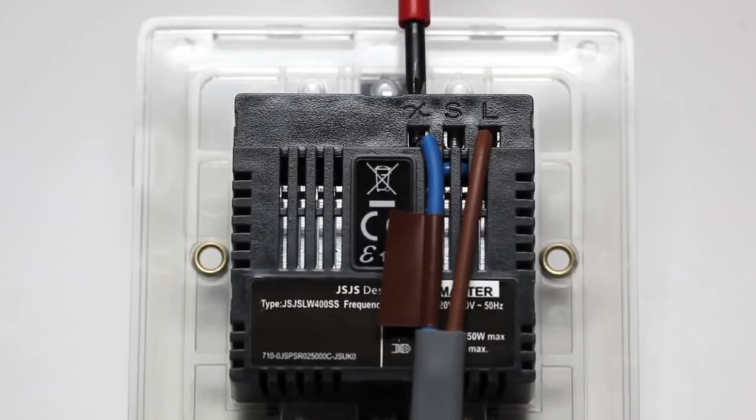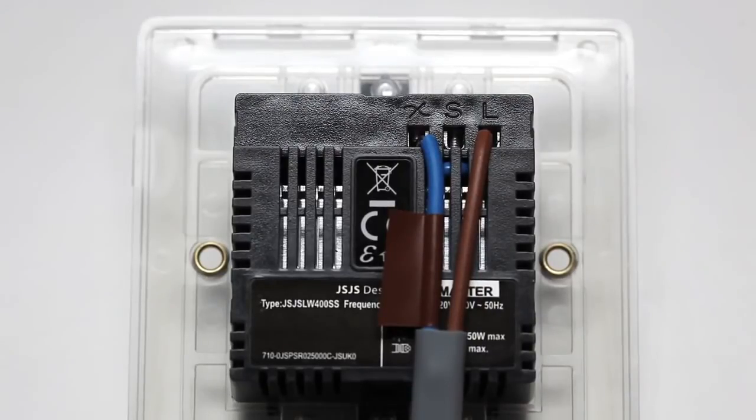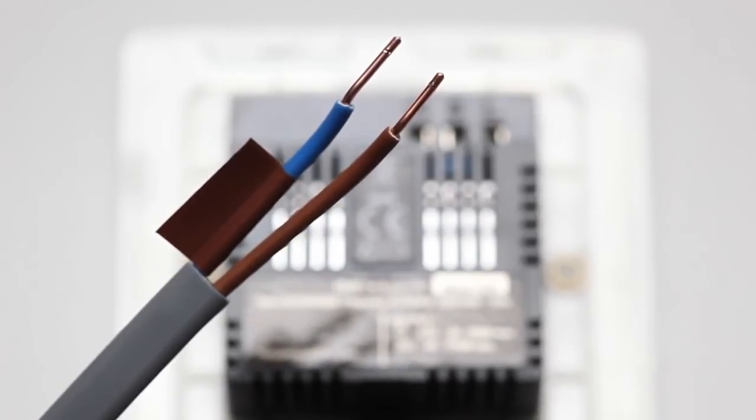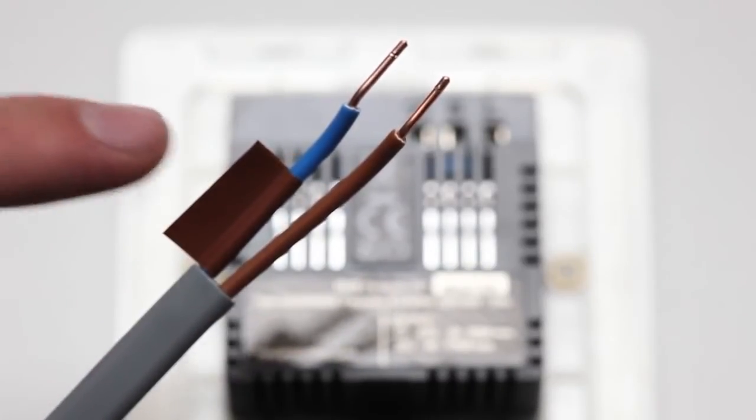Ensure that the terminals are properly tightened and that no bare wire is visible. The LightWave RF dimmer switch doesn't require a mains neutral wire to be connected. It only needs live in and switched live out wires.